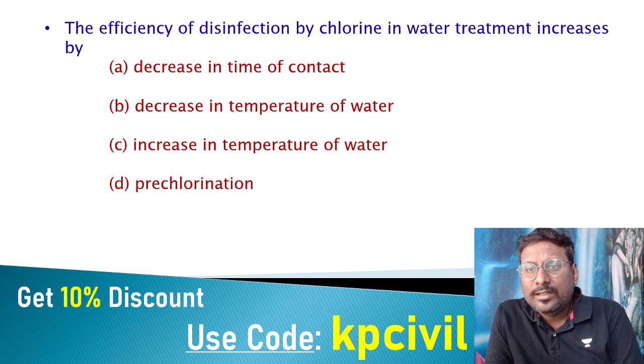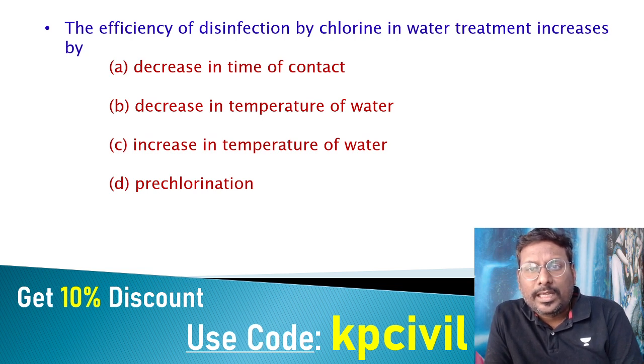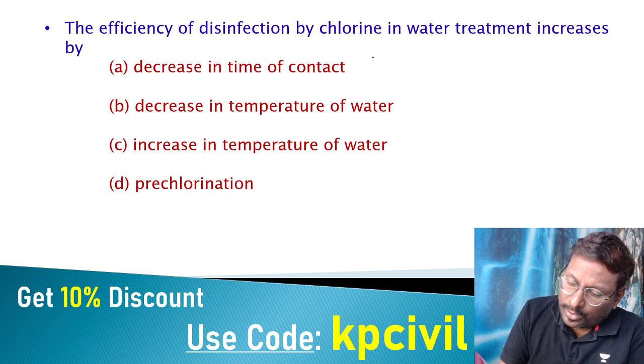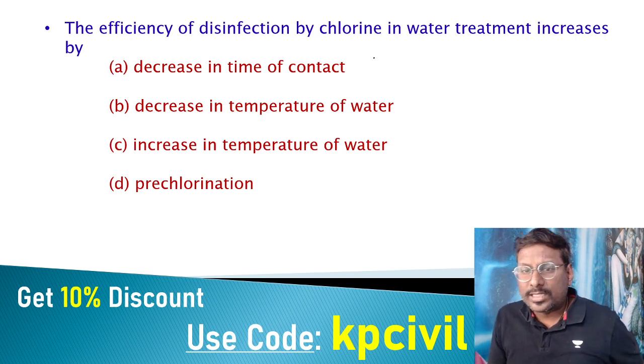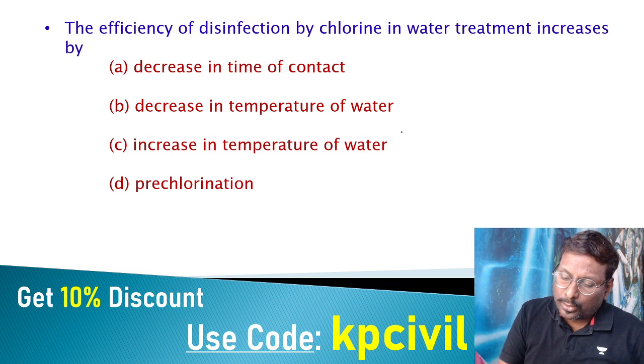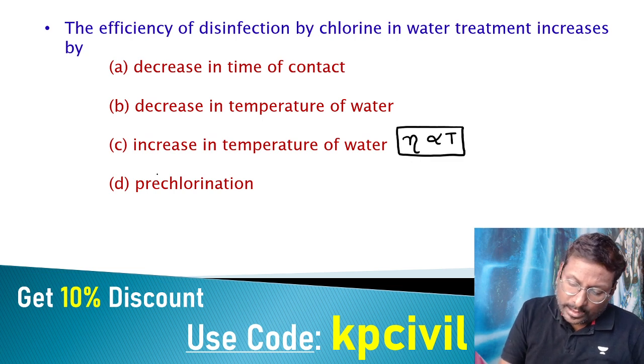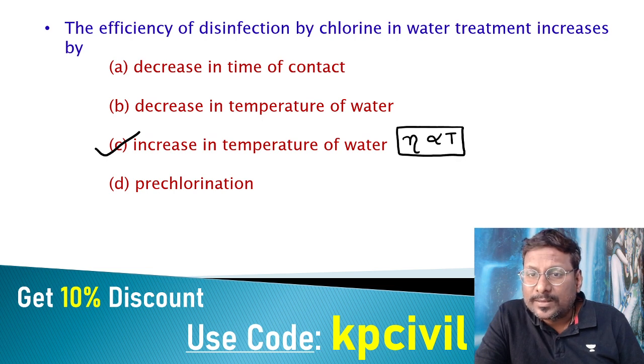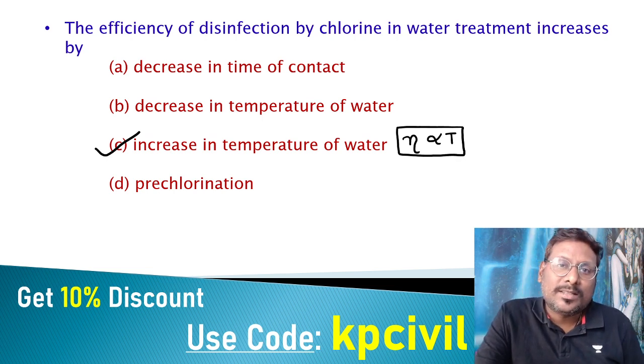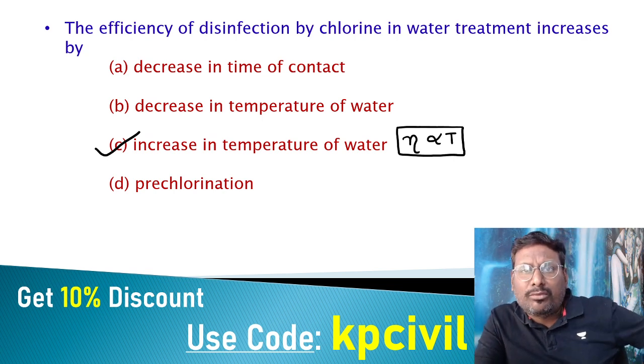Efficiency of disinfection by chlorine in water treatment increases with time of contact — they are directly proportional. More time of contact means more efficiency. Temperature and efficiency are also directly proportional: increase in temperature increases efficiency. Disinfection is a chemical reaction between chlorine and water (formation of HOCl and OCl⁻) and then contact with bacteria. Rate of chemical reaction increases with increase in temperature.